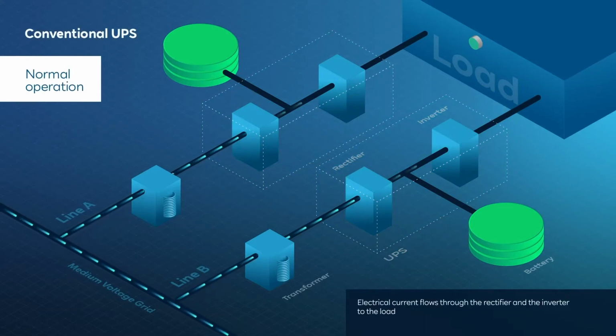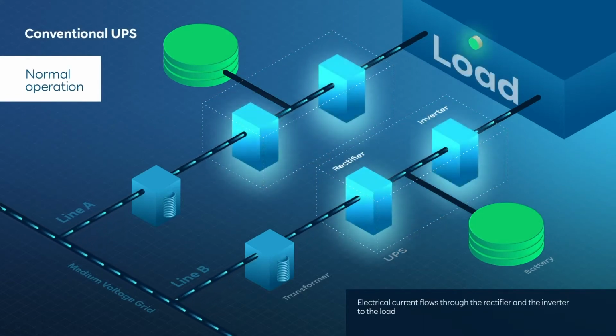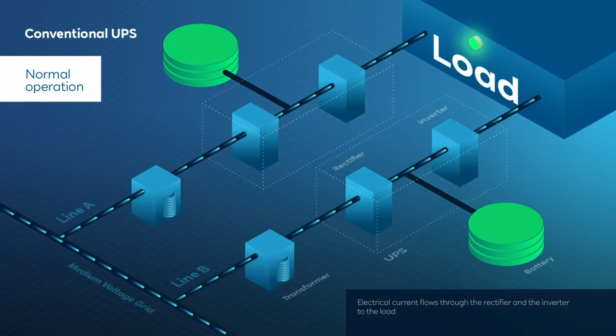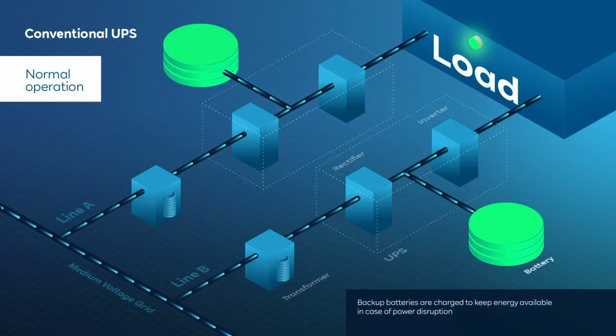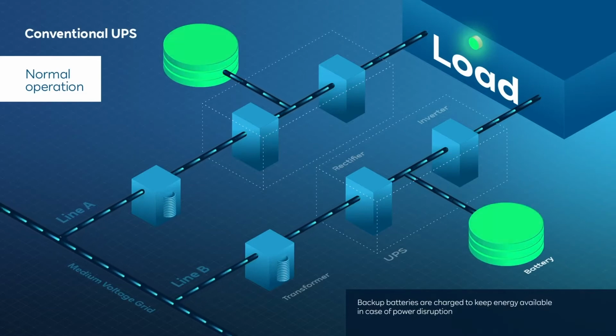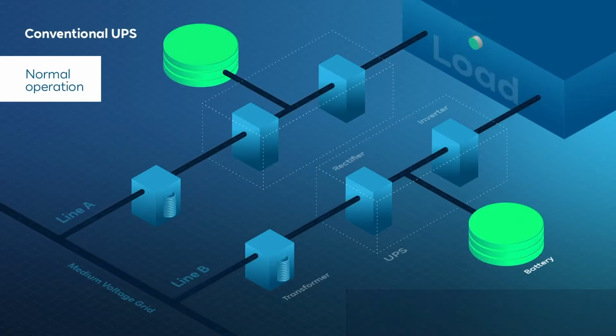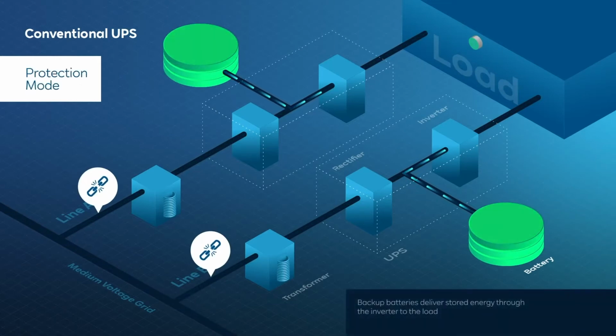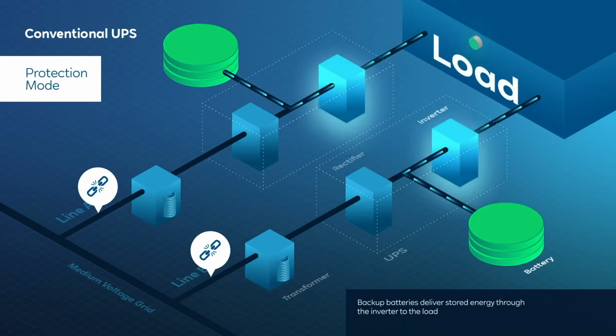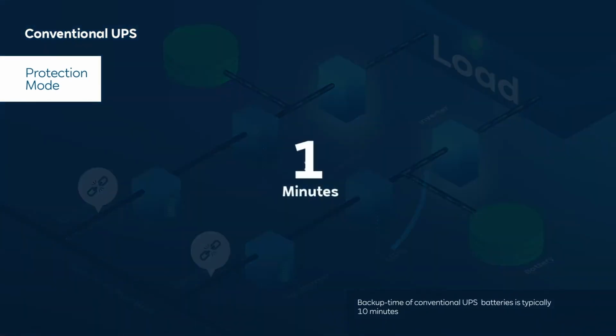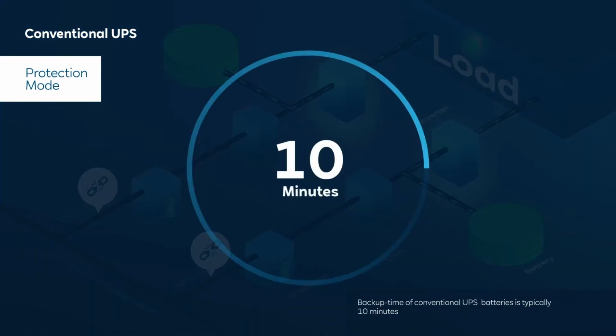When the UPS is in normal operation, the electrical current flows through the rectifier and the inverter to the load. During normal operation, power also flows to the batteries in order to keep backup energy available in case of any power disruption. In case the power supply is in danger, the UPS system switches to protection mode, instantaneously supplying the energy stored in the batteries through the inverter to the load. The backup time is long enough to start a standby power source, for example, an emergency engine, which gives time to the grid to restore normal operating conditions.